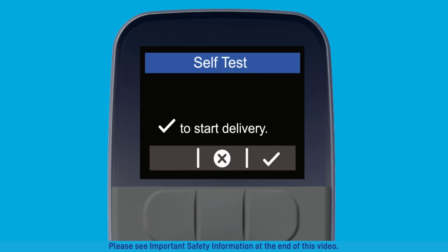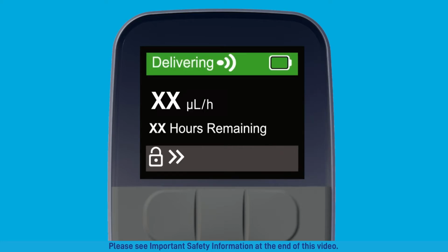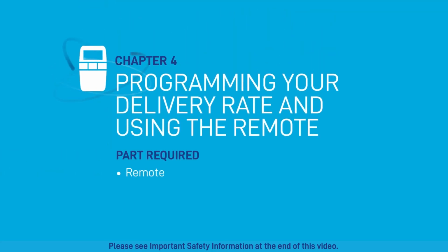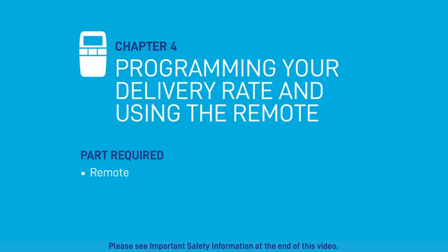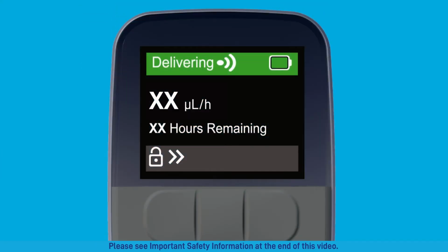The pump will make a 3-tone sound and delivery will start. Your remote will display a green bar to indicate that the pump is delivering. Check to make sure the displayed rate matches your prescribed rate. In this next chapter, we'll cover programming your delivery rate and using the remote. You'll learn what to do if you ever need to change your delivery rate.